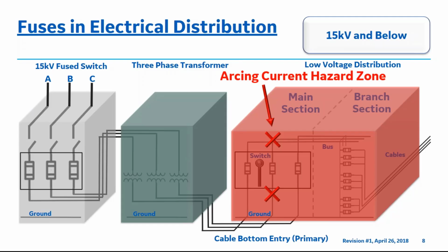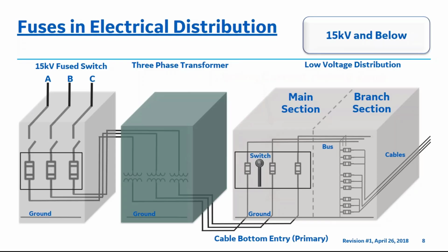The goal of the 2017 NEC 240.67 arc energy reduction paragraph for fuses will begin to address and solve these arcing current problems for 15 kV and below equipment from the utility line side to the point of load. This webinar will focus on topics that help advance technology for humanity, which is the mission and vision of IEEE, the Institute of Electrical and Electronics Engineers, for continued improvement. Let's review the code on the subsequent slide.